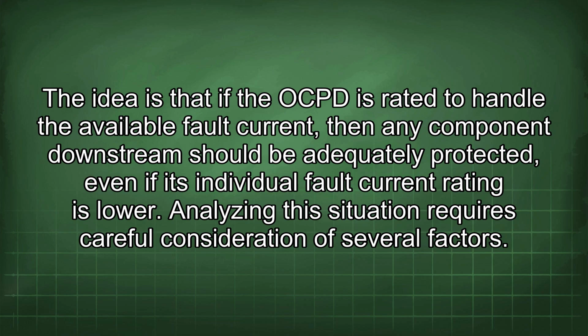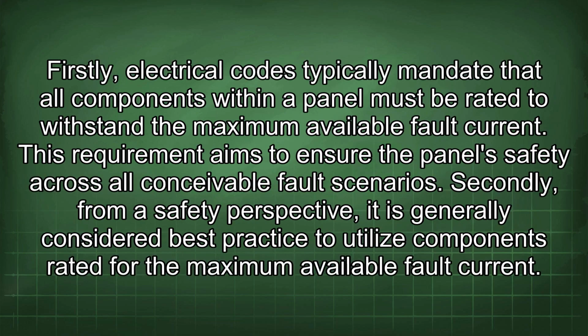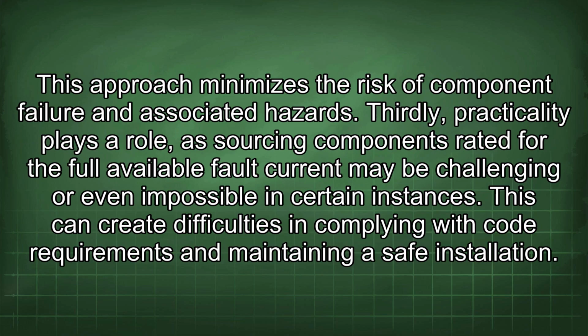Analyzing this situation requires careful consideration of several factors. Firstly, electrical codes typically mandate that all components within a panel must be rated to withstand the maximum available fault current. This requirement aims to ensure the panel's safety across all conceivable fault scenarios. Secondly, from a safety perspective, it is generally considered best practice to utilize components rated for the maximum available fault current. This approach minimizes the risk of component failure and associated hazards. Thirdly, practicality plays a role, as sourcing components rated for the full available fault current may be challenging or even impossible in certain instances. This can create difficulties in complying with code requirements and maintaining a safe installation.